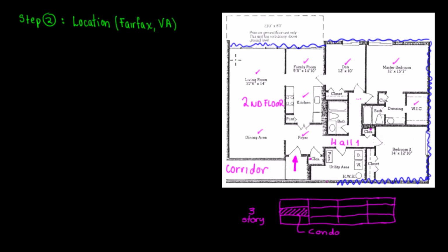If this is a house or a condo unit that was built in the past, and you're a contractor planning to replace the unit, and you need insulation values, and the homeowner says, I don't know what insulation value is, and you cannot perform a heat load calculation like that, then you have to check code. Since we have the location in Fairfax, we're looking at the insulation values, but you need to check also on the year, right? This unit was built like in the 1970s.